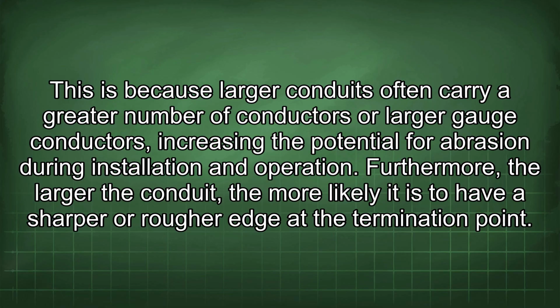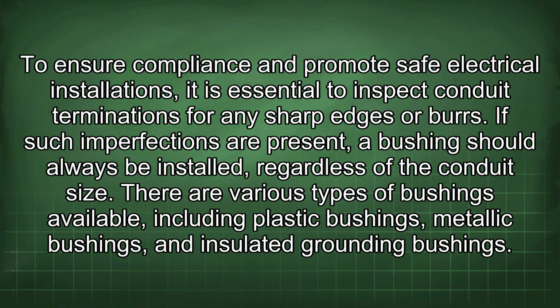Furthermore, the larger the conduit, the more likely it is to have a sharper or rougher edge at the termination point. To ensure compliance and promote safe electrical installations, it is essential to inspect conduit terminations for any sharp edges or burrs. If such imperfections are present, a bushing should always be installed, regardless of the conduit size.